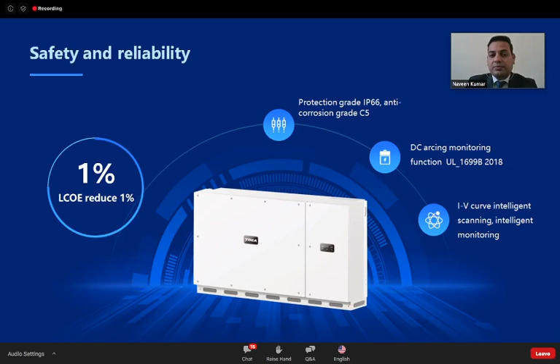Talking about intelligent monitoring of IV curve, our inverter and IV curve monitoring platform can scan 100 megawatt of PV plants within 5 minutes without any generation loss, and the accuracy level is 1%. If you refer to the IV curve I have shown at the bottom, there are 6 types of curve which we can get when there is some problem in your PV module. By doing the IV curve scanning, we can identify which kind of faults we have in our PV module.